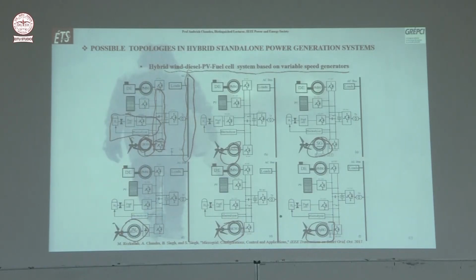This is the DC bus and this is the AC bus. So the fuel cell is connected to the DC bus, the battery bank is there, and then PV is also connected to the DC bus, and the diesel generator using this machine is connected to the DC bus. So this is the interfacing inverter between the DC and AC bus, and power can flow either in this direction or in this direction.